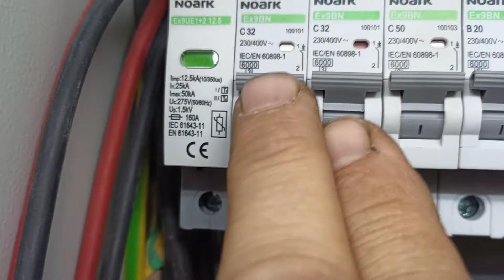And we have the Sunny Boy inverters. Here is the plug - we have again neutral, phase and ground. They come here, the ground and neutral come here, and for the phases we have two 32 amp fuses for these two inverters, and another 32 amp fuse for the other Sunny Boy.